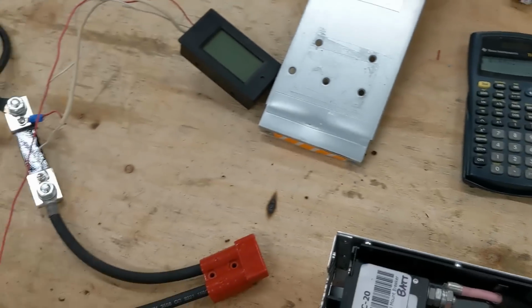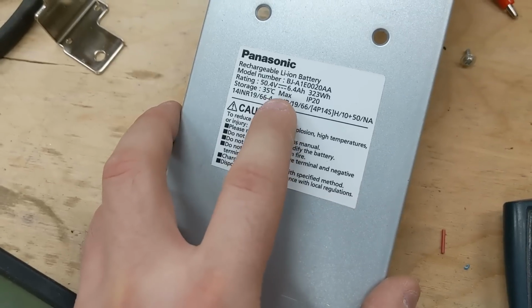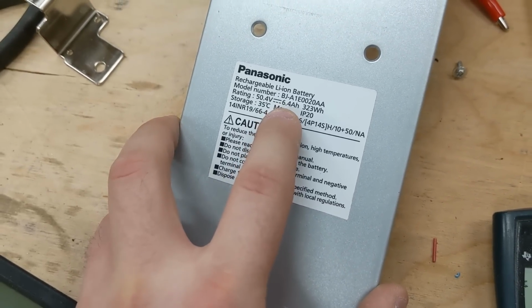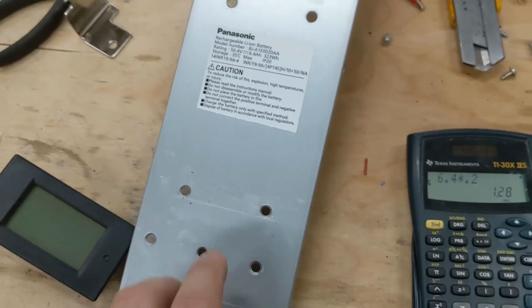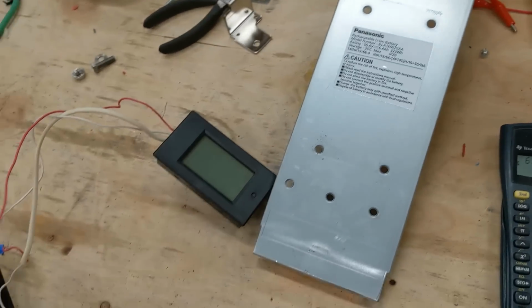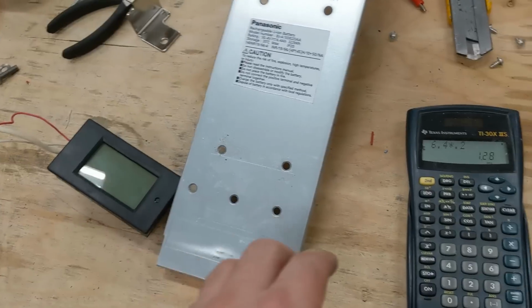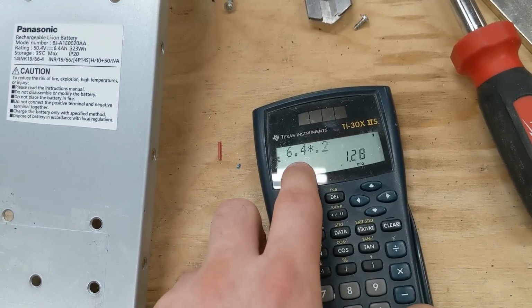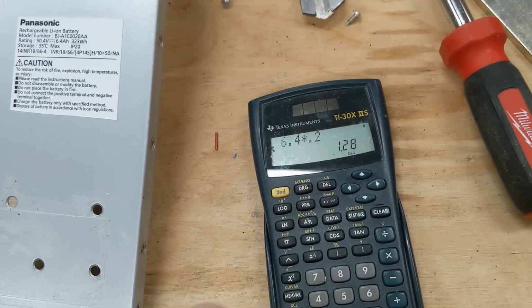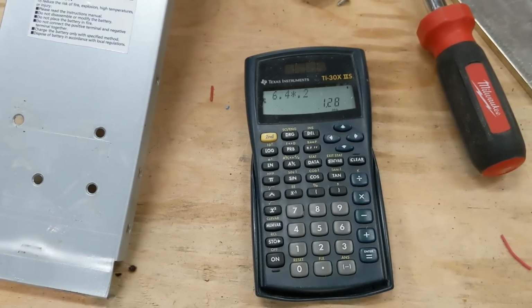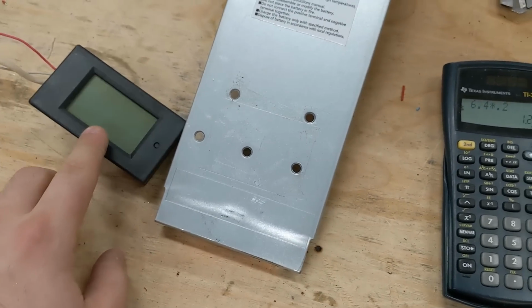Now, how much load do we want to throw on this? Over here we can see that this was a 6.4 amp hour battery, and I think the standard for capacity testing is a 0.2 C rate. So if we multiply that by 0.2, we have 1.28 amps. So that's our goal on here.